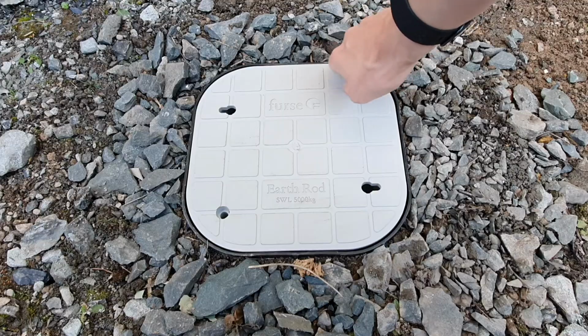However, there are some circumstances where it simply isn't feasible to use an earth reference electrode. Maybe you can't confirm the lack of underground services which could become damaged, or you'd have to drill through perhaps a huge slab of concrete or pavement to get to the general mass of earth. There is another way of meeting regulation 722.411.4.1, and unsurprisingly, the Indra Smart Pro will accommodate this method as well.